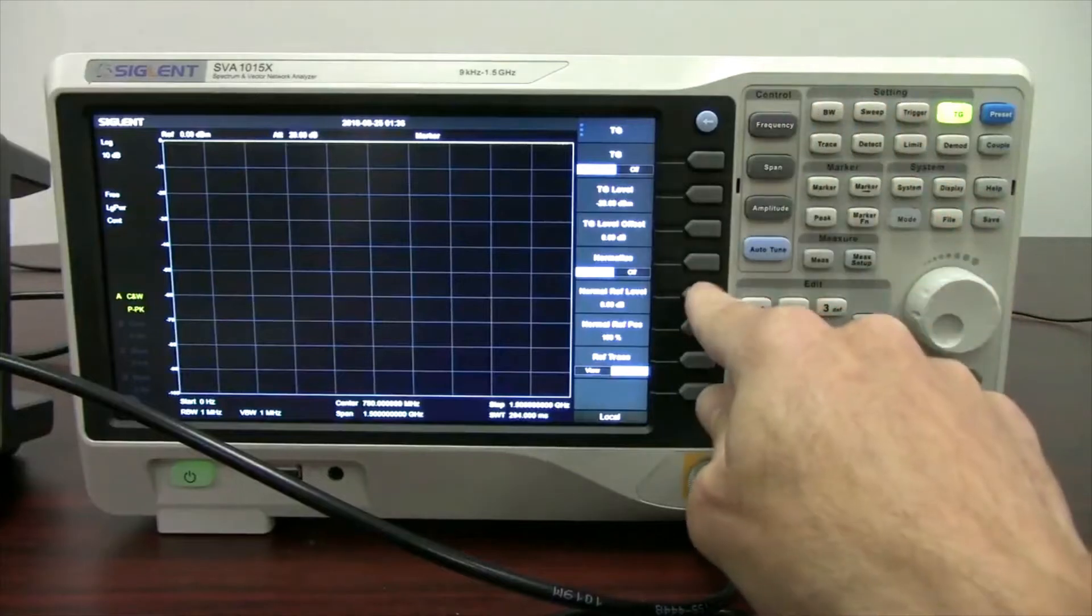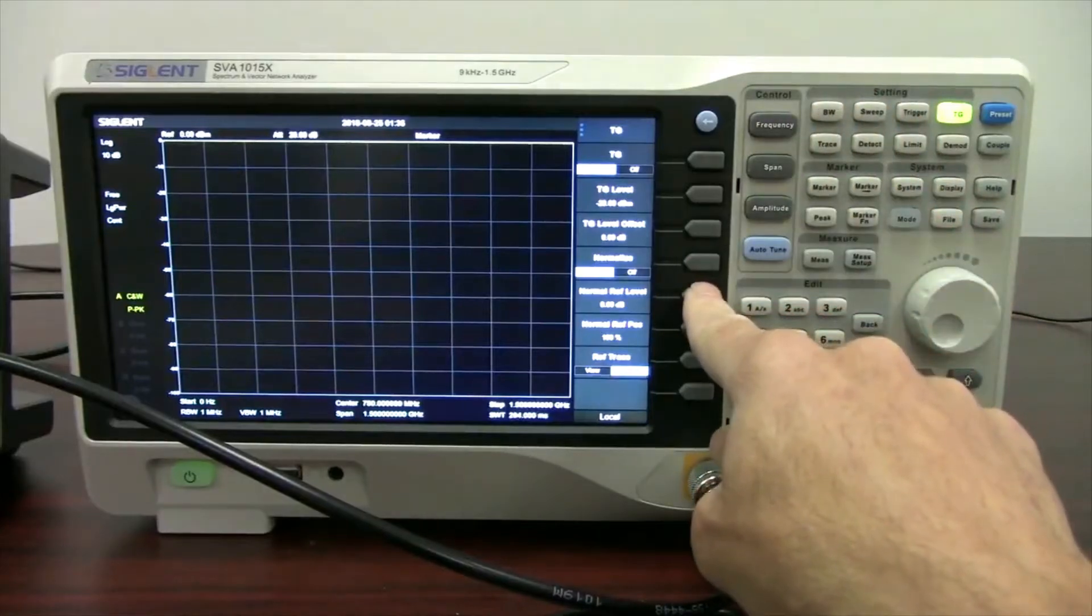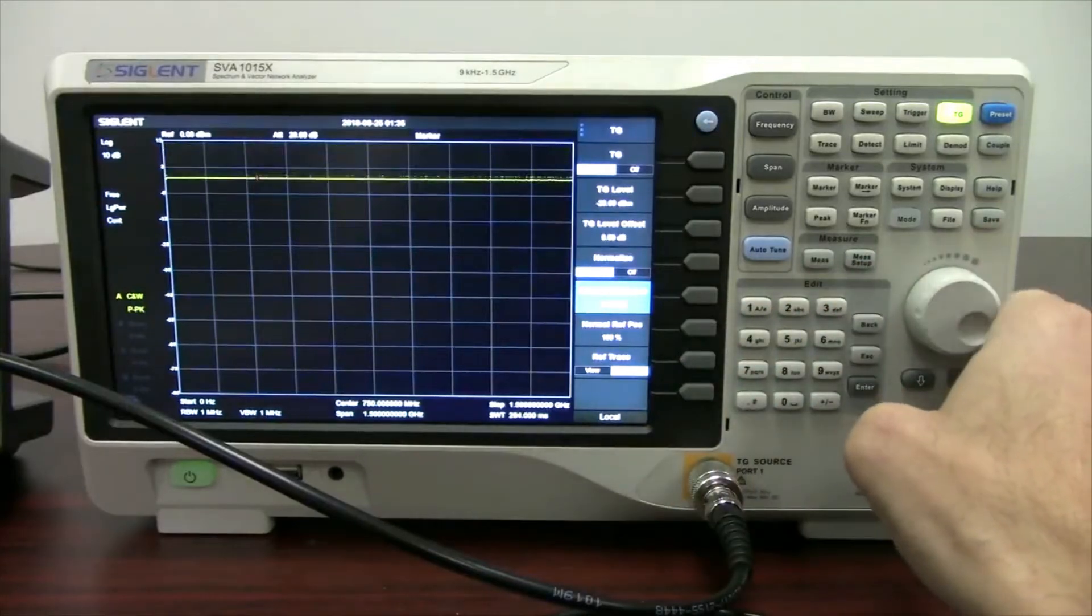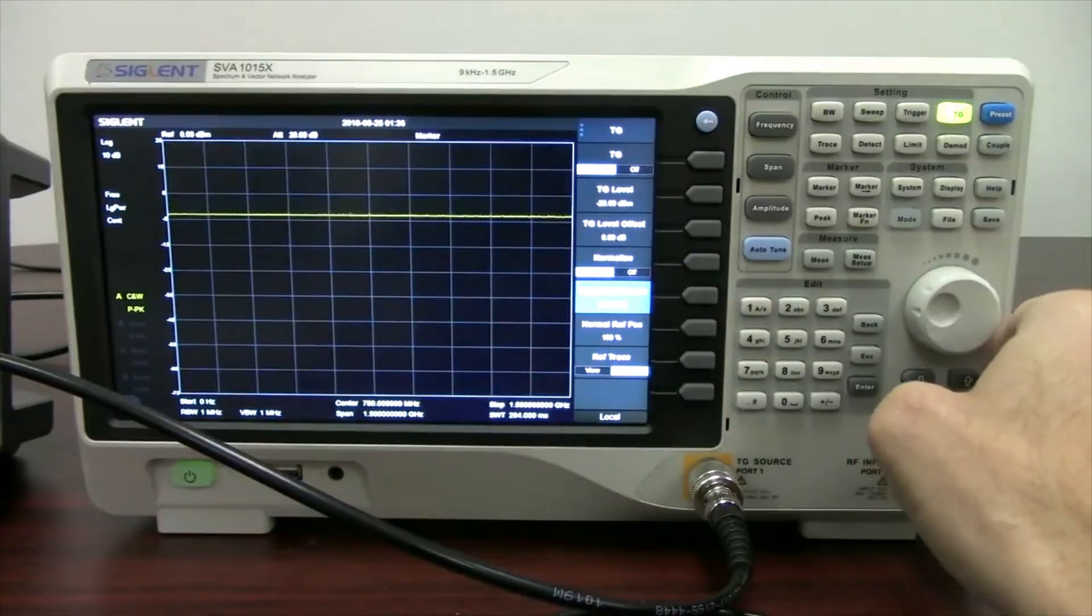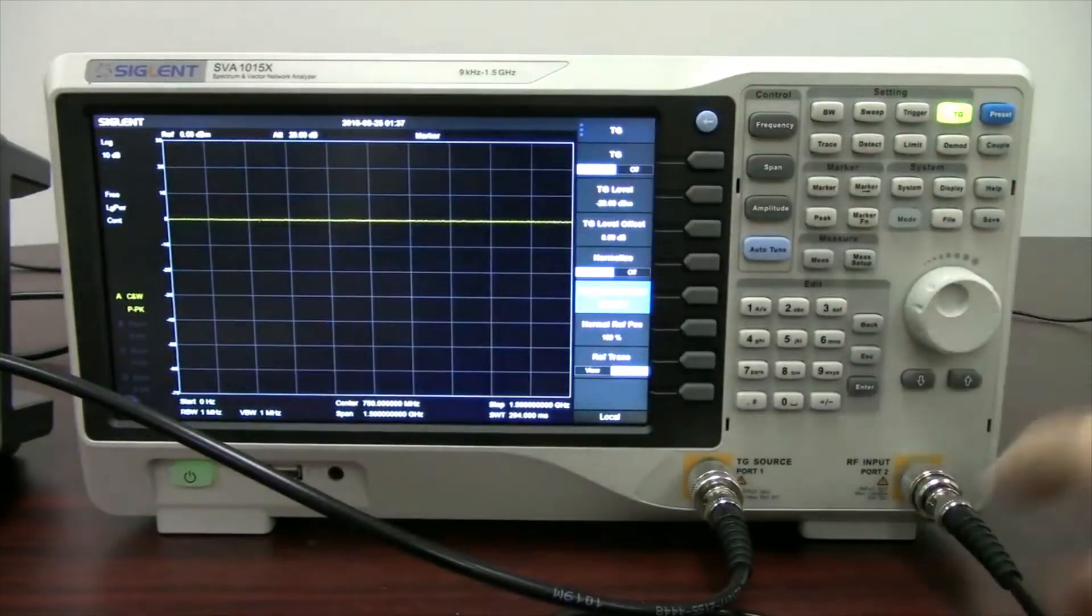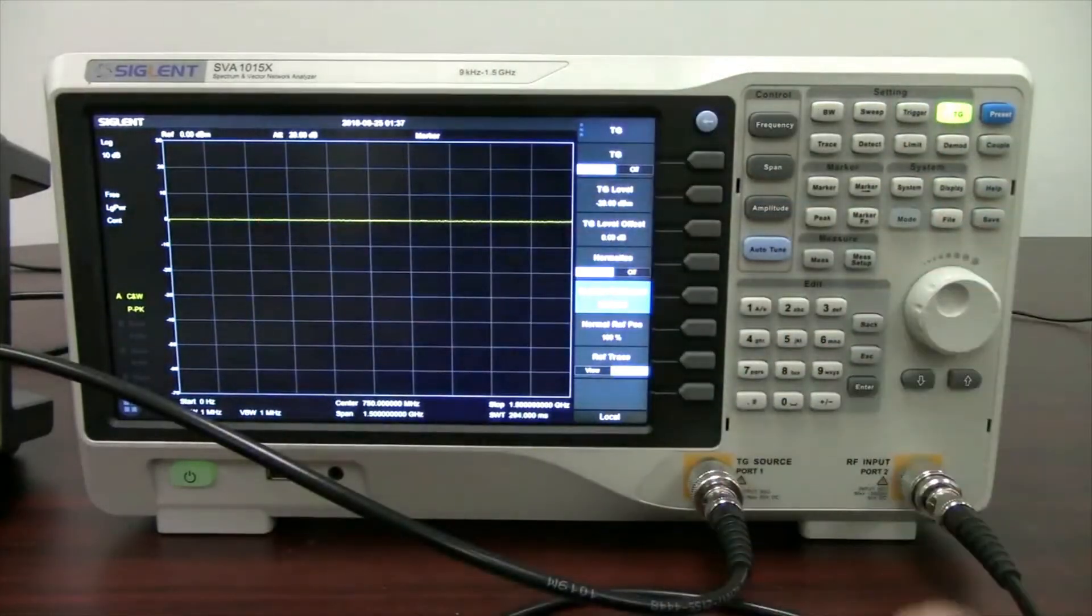Now what we can do is normalize, we can move the normalization reference level. So we're just going to go here and drop it down, and now you'll see that it's a nice flat line. Again, it's at zero dBm, which makes sense because we've normalized all of the losses of the cabling, so we effectively have a relative zero measurement. Now that is with this adapter in place.